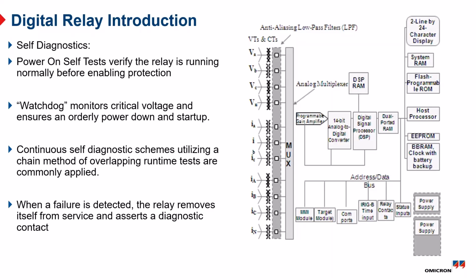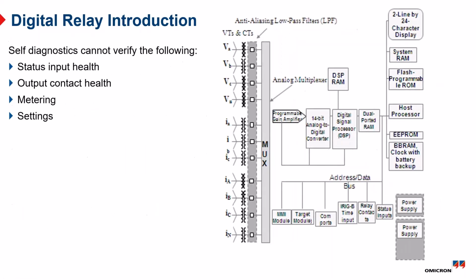You'll see most relays, when you start them up, it clicks and whirs and does its self-diagnostic routine to start up. Part of that is loading the operating code from the flash into the host, and then booting the DSP, and everything goes online in a certain sequence. And once everything is done, the program is released and it starts executing, and the relay OK light turns on, and you're actually protecting. So this self-diagnostic comes into play when they discuss PRC-005. It also comes into play when people design their protection testing programs.